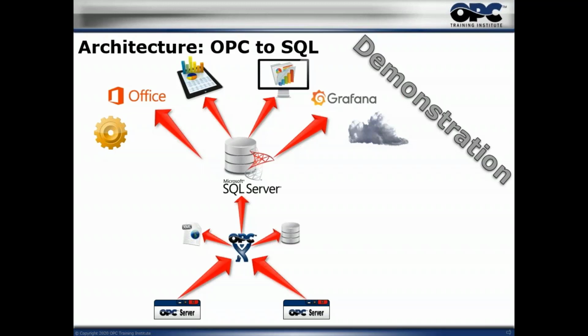In the event of a network outage in between OPC Expert and the database, how is the buffering managed in order not to lose data? So we're talking about the buffering here. I think you asked that question before I explained, but OPC Expert actually manages all of that data in here. Then it sends to SQL Server. As soon as it sends it to SQL Server, and as soon as it receives confirmation the data actually arrived, OPC Expert gets rid of that data it has, and it's in SQL Server in the format that you need, which is actually very, very nice. So nothing for you to actually handle yourself.